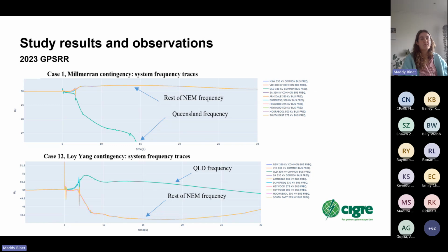So we saw that Moorabool separation with PEC stage 2 included has the potential to cause loss of stability on QNI, which could then be exacerbated by existing remedial action schemes within Victoria and the SAT-RAS due to them tripping additional generation to try and prevent SA islanding. Also, a large amount of UFLS was tripped for a lot of the studies, so potentially more than 4,000 megawatts, which obviously results in a very severe load contingency event.